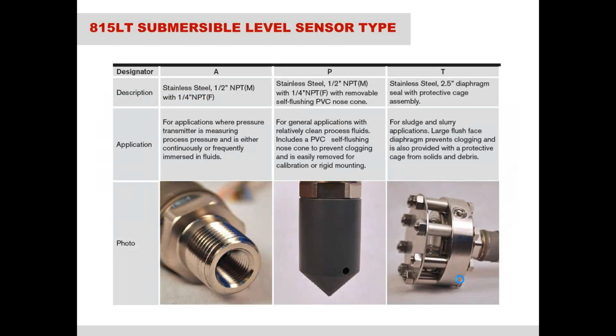For a submersible, we offer the same A process connection as well as the P option, which is a PVC nose cone that is self-flushing. So it protects the cone in there, but it also has a self-flushing port that will prevent any type of clogging from occurring or particulates building up in there. Now, to a certain extent, that will work, but if it's very heavy material, we also have the T option, which gives you a more robust option to prevent against clogging or sludge and slurry applications.